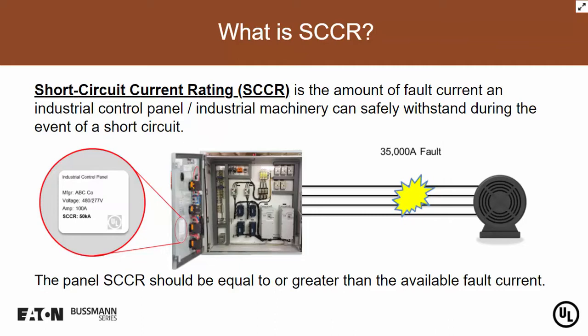It is the amount of fault current an industrial control panel or industrial machinery can safely withstand during the event of a short circuit. So what you see in this particular slide is an industrial control panel. It has a label. That label would be the main nameplate, which is generally provided on the outside of the enclosure door. If it's on the inside, it's on the enclosure door as well, so that it is clearly visible. As part of the nameplate, you would find the short circuit current rating. And you can see in this example here, the short circuit current rating is 50,000 amps.